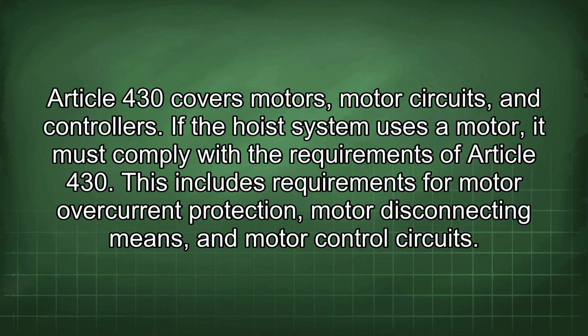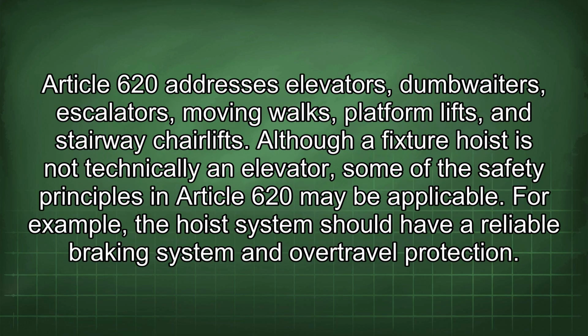Article 430 covers motors, motor circuits, and controllers. If the hoist system uses a motor, it must comply with the requirements of Article 430. This includes requirements for motor overcurrent protection, motor disconnecting means, and motor control circuits. Article 620 addresses elevators, dumbwaiters, escalators, moving walks, platform lifts, and stairway chair lifts. Although a fixture hoist is not technically an elevator, some of the safety principles in Article 620 may be applicable. For example, the hoist system should have a reliable braking system and over-travel protection.